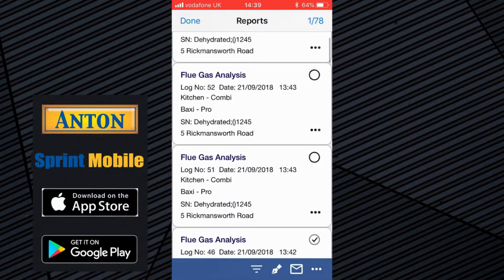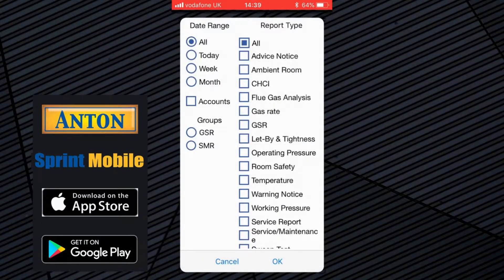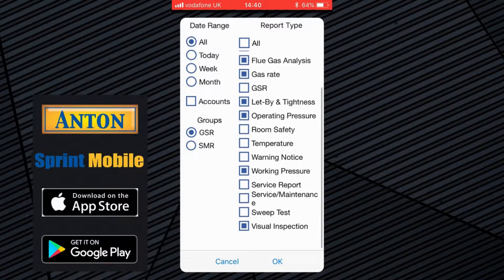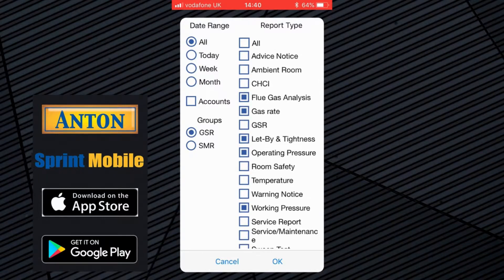Let's just undo those for a second. If you go into the filter button, which is in the middle of the blue bar at the bottom there, you have got lots of choices. So GSR — gas safety record group — you can click that and it will only then list the flue gas analysis, gas rates, let-by tightness, operating pressure and working pressure. So in other words, no visual inspections. Those are the reports that could provide data and populate the landlord gas safety record — just to show you that as a nice feature.